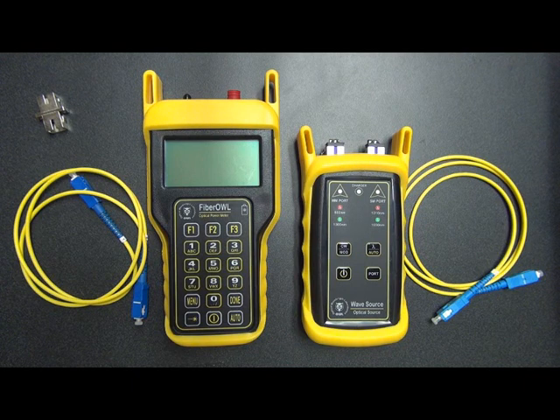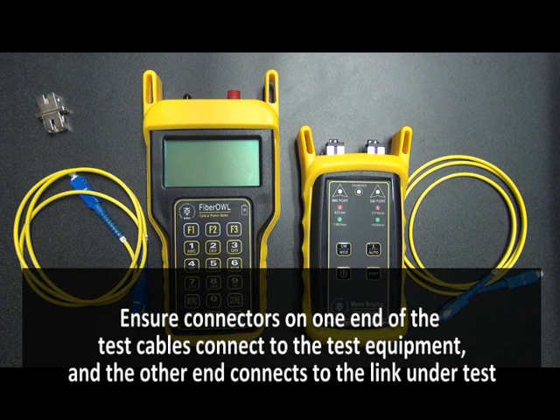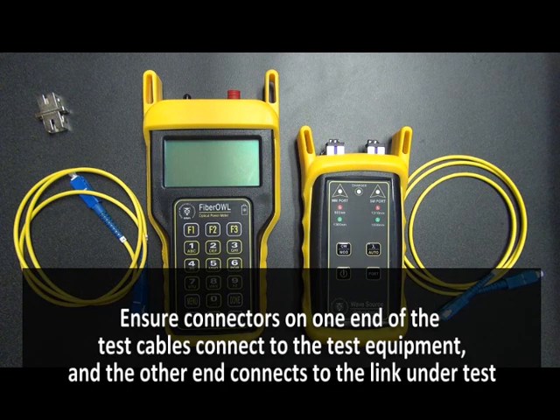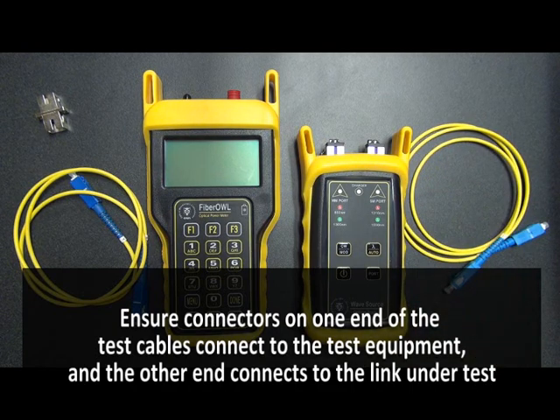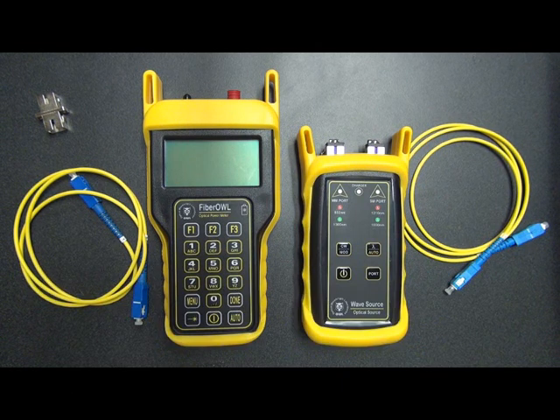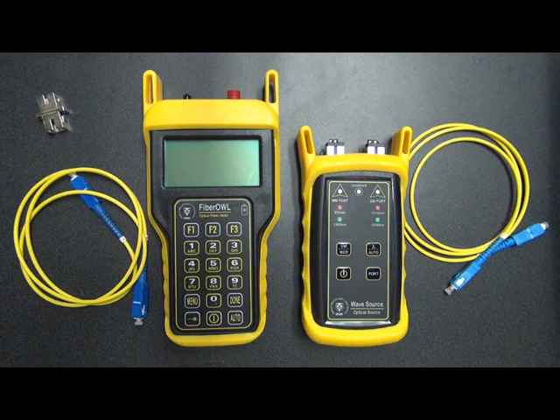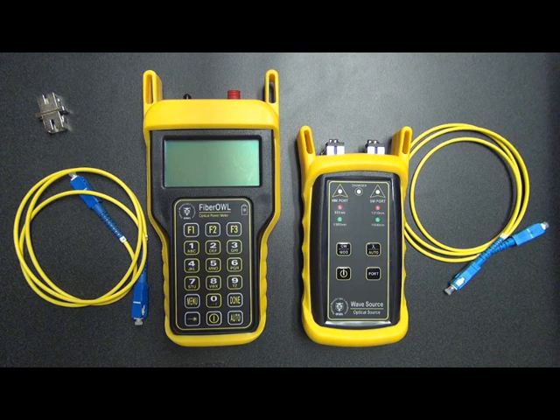One thing to make sure of when choosing test cables is that the connector types match the testers and the patch panel that you're going to be testing. They might not be the same, so one end of the patch cable needs to be able to connect into the testers and the other end needs to connect into the link under test. This could be SC to LC, SC to ST. It doesn't have to match. For this purpose, we're just going to assume that the patch panels are SC.